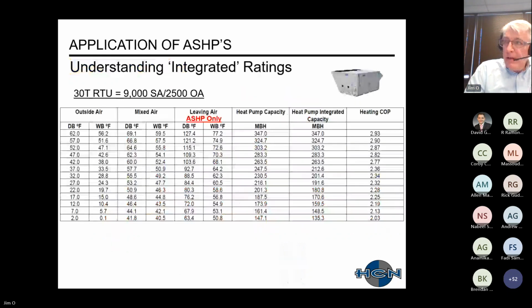Next, I just want to talk about your air source heat pump output tables. This one here is just typical of what I've seen. On the left, you have outside air with different bin temperatures in 5-degree steps. For this application, I had about 25% outside air, so there's the equivalent mixed air temperature. Next, going from left to right, we have our leaving air temperature. I want to emphasize that this is the leaving air after the air source heat pump. The next two tables are heating capacity.